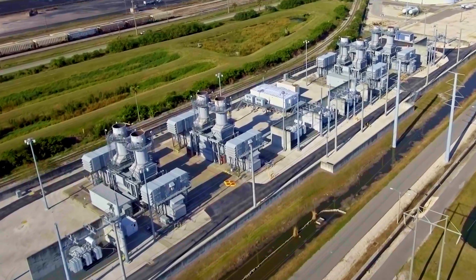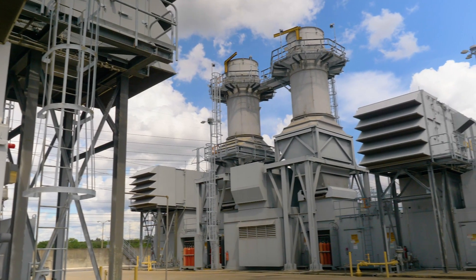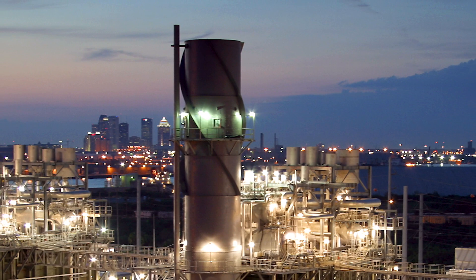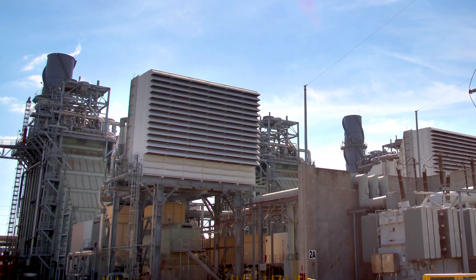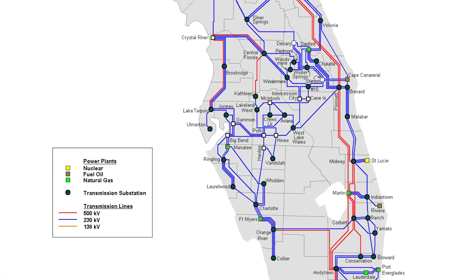There's more to Bayside than units one and two. In 2009, four aero natural gas peaking units were installed. The peakers support Tampa Electric's commitment to provide reliable power, generally running when there's high demand — for instance, when customer demand spikes due to extreme weather or major outages. Each peaker is made up of two 30-megawatt engines. Power from the peaking units can start Bayside's larger generating units during a blackout when grid power isn't available — this is called Black Start. Their quick start ability means the company can bring them to full load status in 15 minutes, an economical way to maintain required operating reserves and respond to statewide system disruptions.